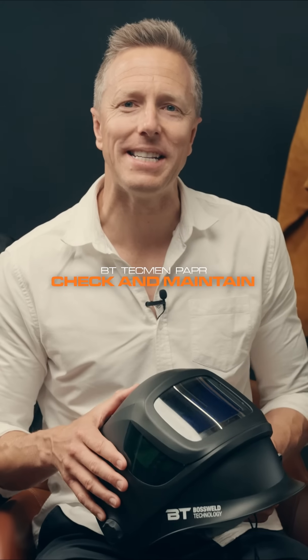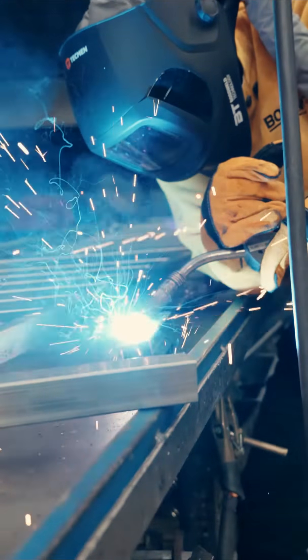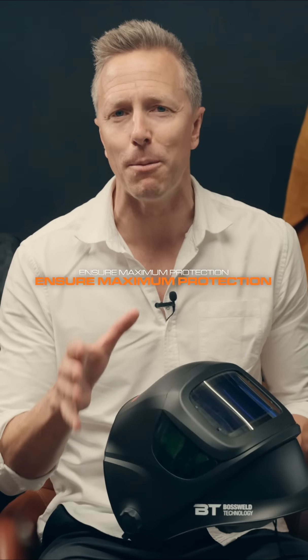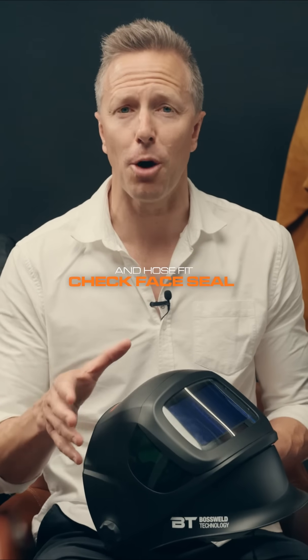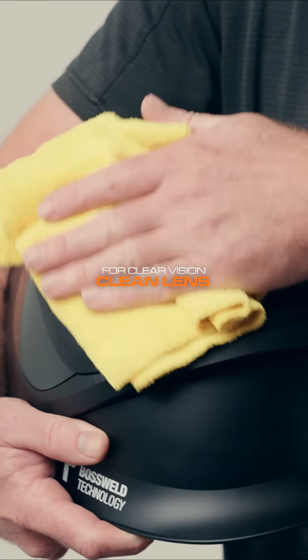Hi there. Today we're going to explain how best to check and maintain your BT Tecmen powered air purifying respirator system. Prior to using your BT Tecmen unit, it's always a good idea to conduct a pre-use inspection to ensure the unit is going to provide you with optimum protection. Ensure the head top is in good working order. Test the lens is working properly by turning the auto-darkening screen on. Check the face seal is secured properly. Ensure the hose is correctly fitted to the head top.